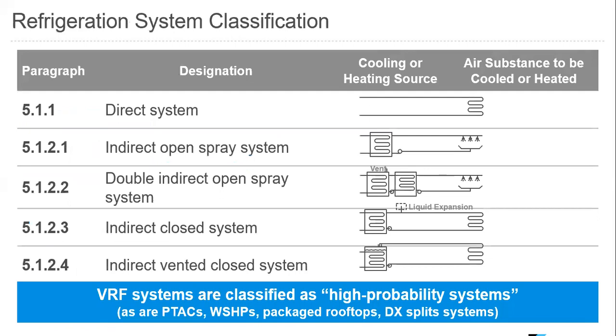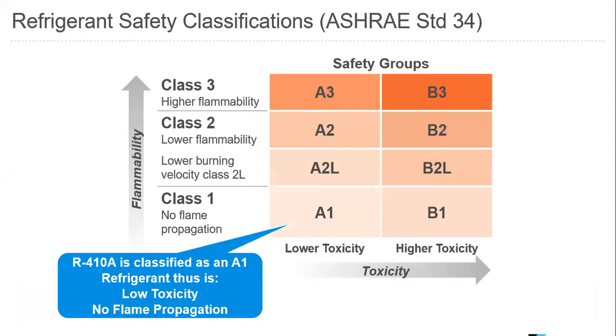So there are 5 key different types of systems defined in ASHRAE 15. We have a direct system, an indirect open spray system, a double indirect open spray system, an indirect closed system, an indirect vented closed system. And VRF systems are classified as high probability systems, as are other equipment types such as PTACs, water source heat pumps, packaged rooftops, and DX split systems.